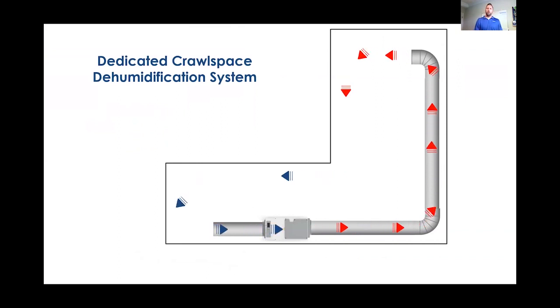Now, I drew this up from a crawl space, a dedicated crawl space system. So if you have a dirt floor crawl space, I would caution you in putting a dehumidifier in there because you'll actually start drawing the moisture through the ground. So I would say once you have a full encapsulation, put your dehumidifier system in that space. But if you have one of these L-shaped ranches or even a very long ranch, I recommend putting some ductwork on it because then you're getting that air movement circulating through that crawl space. If I don't put the duct, it's not required. So don't think that this is 100% what you have to do. But if I take this ductwork off, my area of condition is going to be potentially less than what I'm doing here. You can see I'm pushing the air out and it's cycling back to the dehumidifier here. So just wanted to give you some visualization on that.